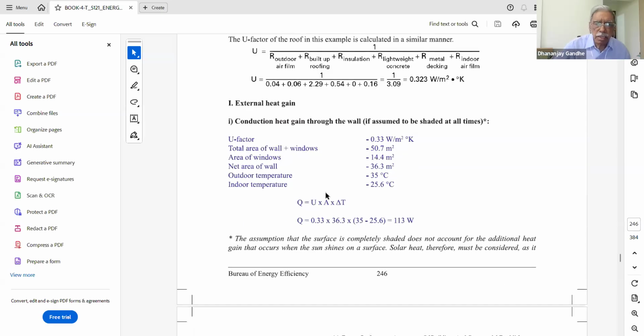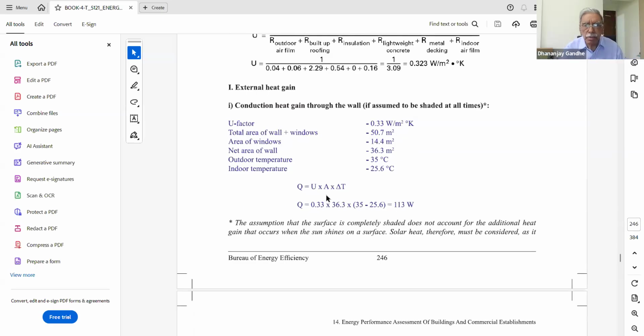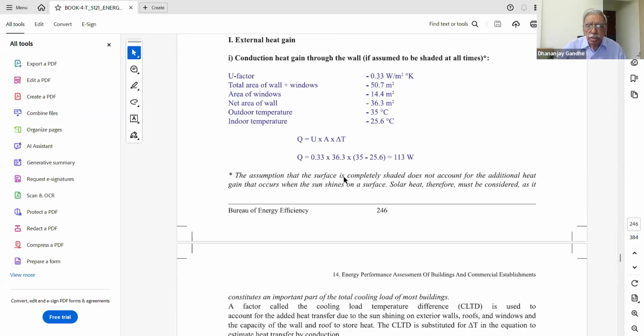And then the external heat gain from the wall, from outside, can be calculated like this. The U factor value mentioned is 0.33. The area mentioned earlier is also 50.3. Area of the windows is 14. Net wall area is 50.3 minus 14, that is 36.3. Outdoor temperature is 35. Inside temperature to be maintained in the air conditioning is 25.6 degrees.